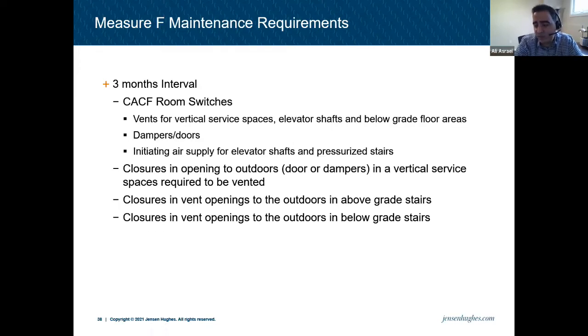And when it comes to measure F, they're slightly different because there are different areas that are pressurized, so elevator shafts, below grade floor areas and all that. So there are vents and the switches from the CACF room, and you have to confirm all that. One thing to note here: if nobody provided that switch from the CACF room, we usually recommend it, because it was approved at the time with the design that way, right? So there are certain things that we usually recommend, and most people take it and do it. But other than that, I don't think we can do anything because this is an existing building, unless there is an issue with the design and performance of the system that we have to raise.